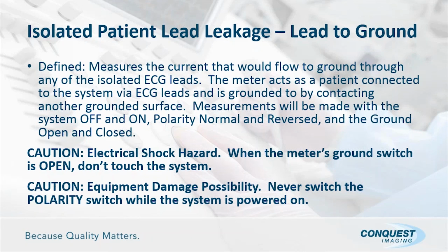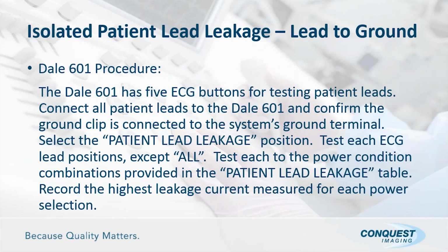Also equipment damage, again, with a polarity switch. You can't go from normal to reversed without first shutting the system down manually. Then for lead leakage, or lead to ground leakage, you can use the Dale 601 again. It has 5 ECG buttons for testing patient leads. Another question I get: well, I only have a 3-lead system. That's okay. You just connect the 3 leads to the tester. Make sure the ground clip is connected to the system's ground terminal.